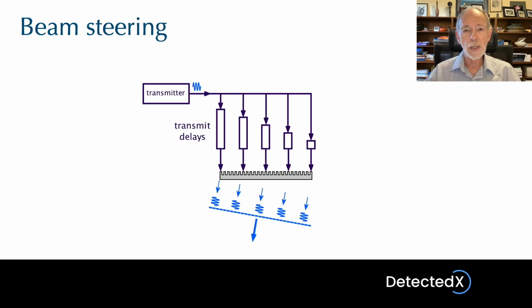Steering the beam is necessary sometimes. It's required for Doppler ultrasound because the angle between the beam and the direction of blood flow is a critical parameter in Doppler ultrasound. It's also required for some specialized modes of operation, such as compound scanning. So, as I said, steering the beam means pointing it in different directions, and I've shown one particular direction here. Now, at the moment, we're not including focusing in this picture, so this is looking purely at steering the beam.